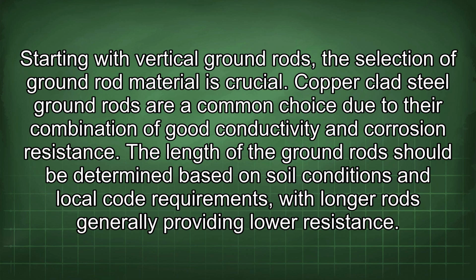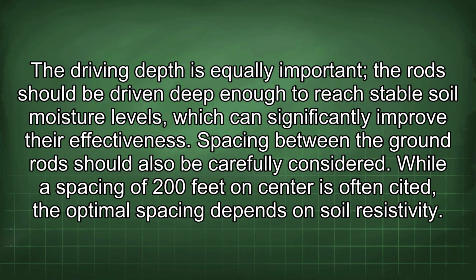Starting with vertical ground rods, the selection of ground rod material is crucial. Copper-clad steel ground rods are a common choice due to their combination of good conductivity and corrosion resistance. The length of the ground rod should be determined based on soil conditions and local code requirements, with longer rods generally providing lower resistance. The driving depth is equally important. The rods should be driven deep enough to reach stable soil moisture levels, which can significantly improve their effectiveness.